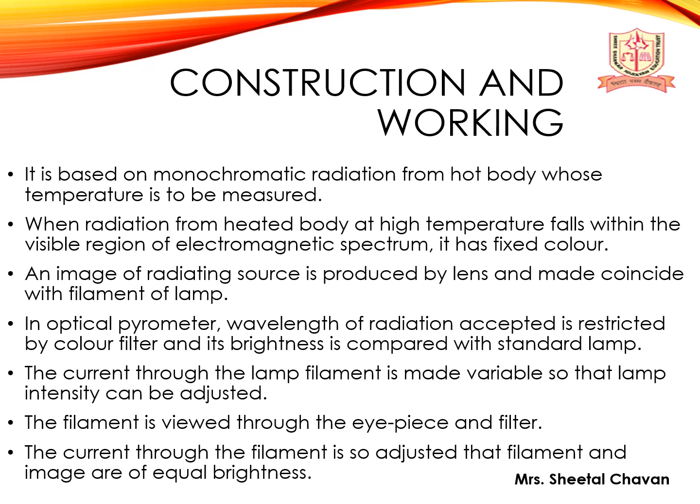Construction and working. It is based on monochromatic radiation from hot bodies whose temperature is to be measured. When the radiation from a heated body at high temperature falls within the visible region of the electromagnetic spectrum, it has a fixed color. An image of the radiating source is provided by the lens and made to coincide with the filament of the lamp. The wavelength of radiation accepted is restricted by a color filter, and its brightness is compared with the standard lamp. The current through the lamp filament is made variable so that the lamp intensity can be adjusted.